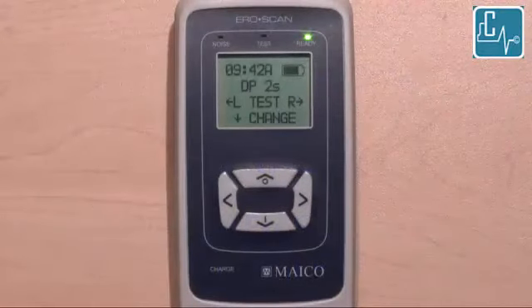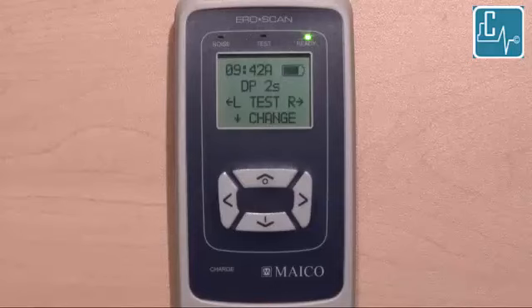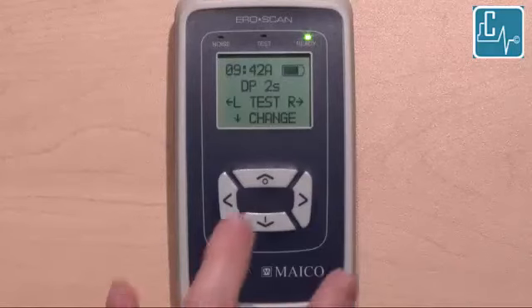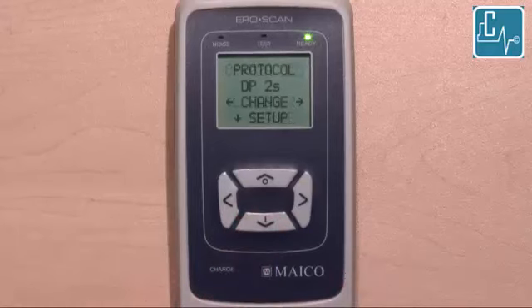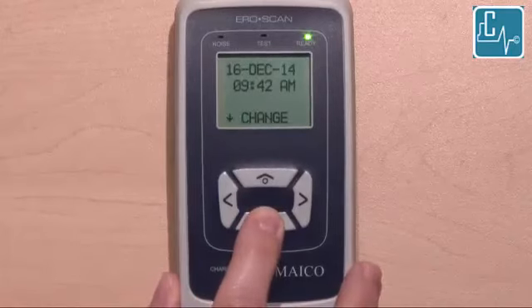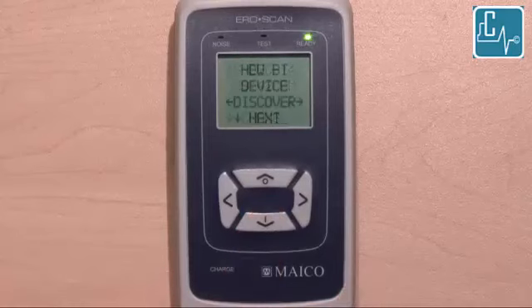The pairing of the ERO SCAN to the optional thermal printer is completed in the Setup menu. Press the down Change arrow from the main test screen. Press the down Setup arrow. When Change is displayed with the date and time, press and hold the down arrow key for 3 seconds until the green ready light at the top of the device goes out. This will bring you to the pairing menu.